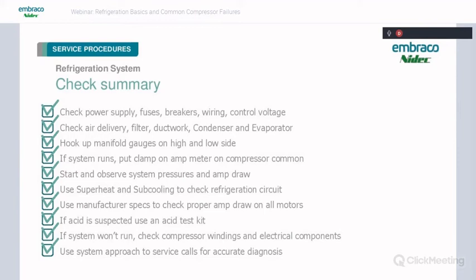If the system runs, go ahead and put a clamp-on amp meter on the common of the compressor. Start and observe the pressures and the amp draw. And then use superheat and subcooling to check and see if we're evaporating and condensing correctly in the refrigeration circuit. And then use manufacturer specs to check for the proper amp draw on all the motors. If we suspect there could be acid in the system, you can always use one of those 2-second acid test kits that they sell at the supply houses. They're very handy. If the system won't run, go ahead and check the compressor windings and the electrical components. Make sure everything's tight in the electrical department. And basically, this is just using the system approach to service calls for accurate diagnosis. So we're not changing out good compressors and sending them back to Embraco.